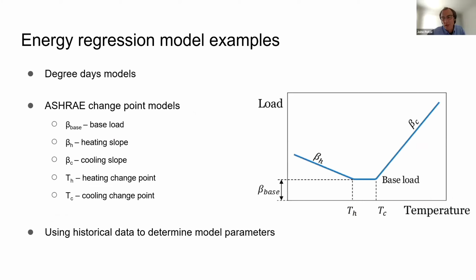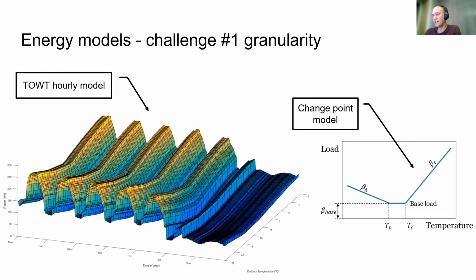Not sure, but why don't you explain? Yeah, I can comment on both of these. I think that in this case, this is just an illustrative example, and this is a building that uses energy for heating as well as for cooling. And in this case, this 3D chart, I know this building by heart, is one big office building in the Czech Republic. This is the European style of weekday, so we are starting with Monday. You can see 5 days with higher consumption and lower consumption over the weekend with a small peak on Saturday morning. Okay.